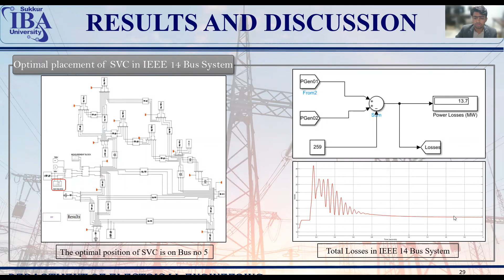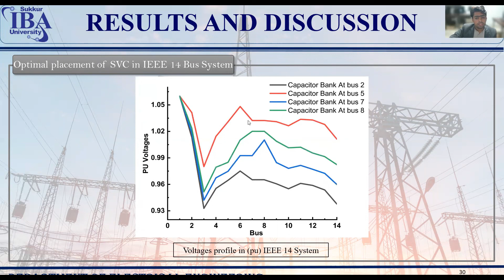This graph shows the voltage profile of the IEEE 14 bus system. After designing the IEEE 14 bus system in PSCAD software, we start placing capacitor banks on each bus. And we come to know that the best optimum position for the placement of SVC is bus number 5, in which we have placed a capacitor and found that the voltages are enhanced, the reactive power flows maximum from the capacitor here, and the losses are very minimized.